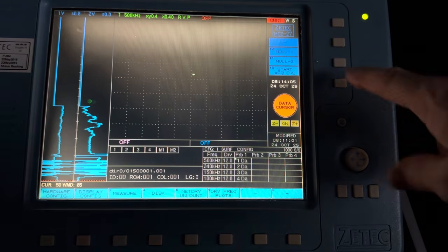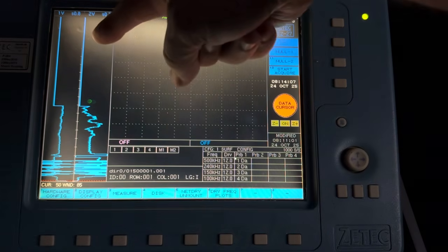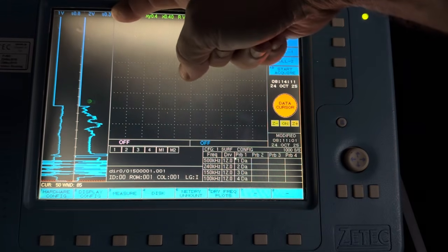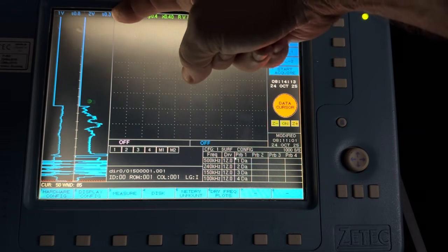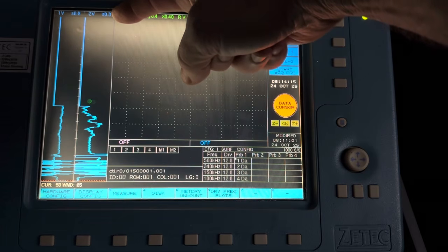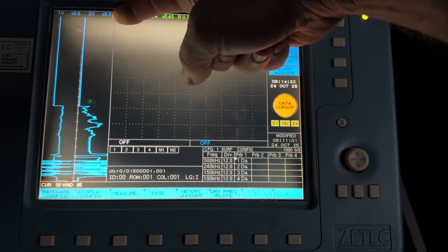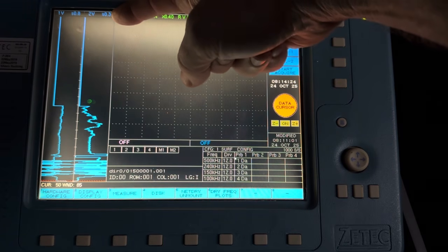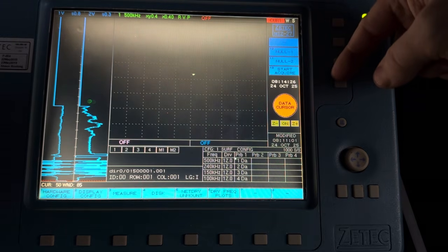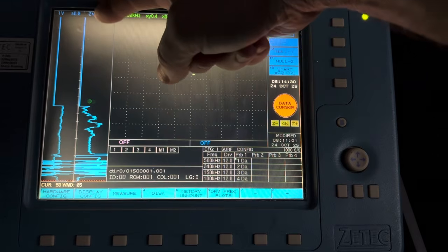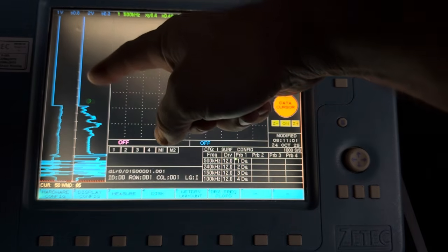So what I'm going to do is start the tester, and I want you to pay attention to the strip charts over here. Now, the strip charts are an indicator of time, which can be used to estimate distance, and also it's useful for determining the location of flaws with respect to either tube ends or support structures like tube support plates. Now, when I start the tester in the recording mode, you're going to see that this data starts to play in from the top as it's recorded.